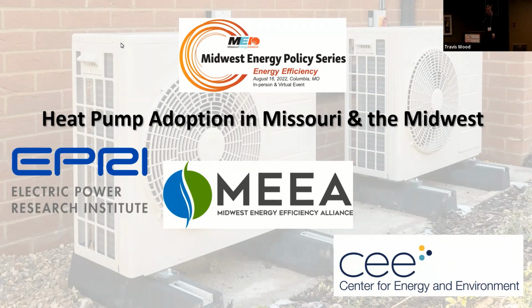So the edge of ground source heat pump technology is looking at ways to make communities ground source, to have a district type system. And even then, to look at existing district systems in cities and try to replace coal and gas fired district heating systems with ground source heat pumps that derive their heat not necessarily from a bored ground loop, but from a nearby water supply, maybe a river or lake. So yeah, ground source is a fantastic option in terms of efficiency, if you can get the cost to work.